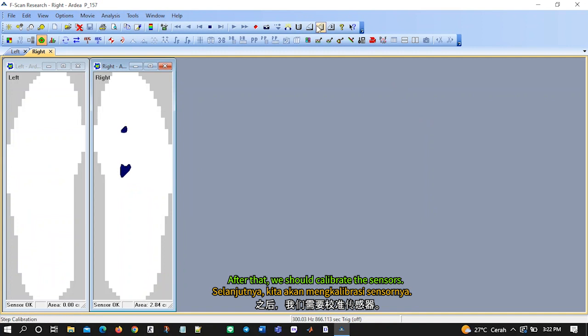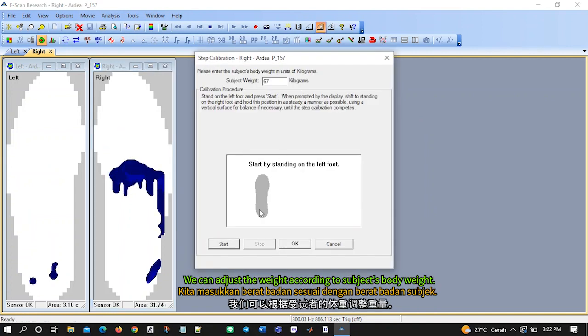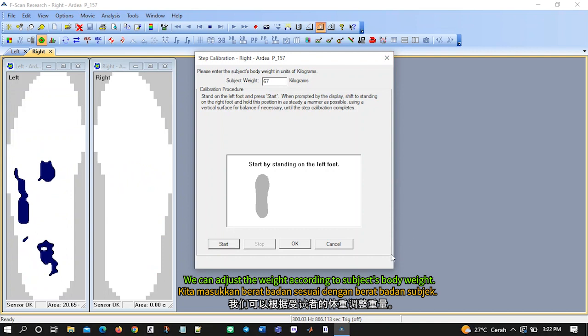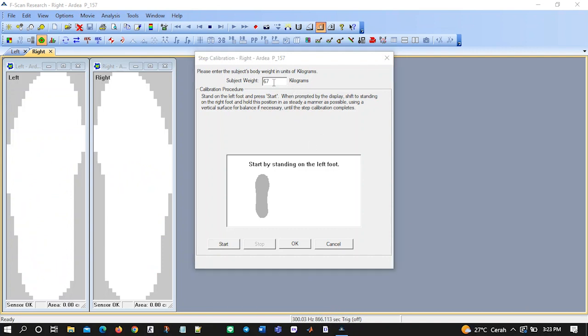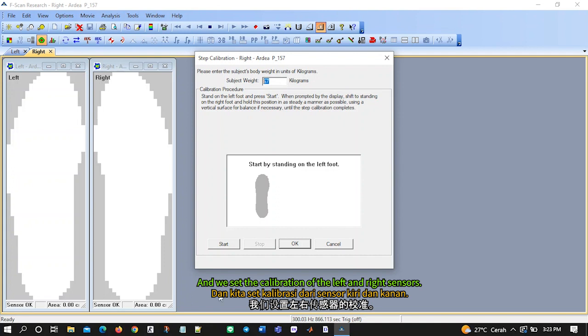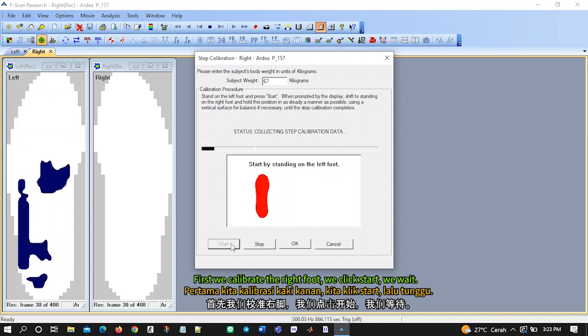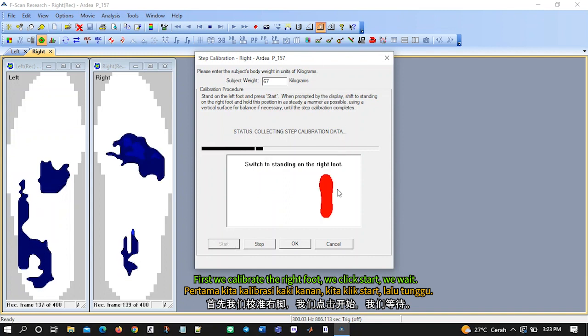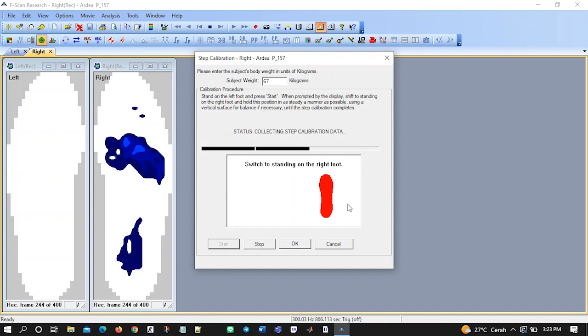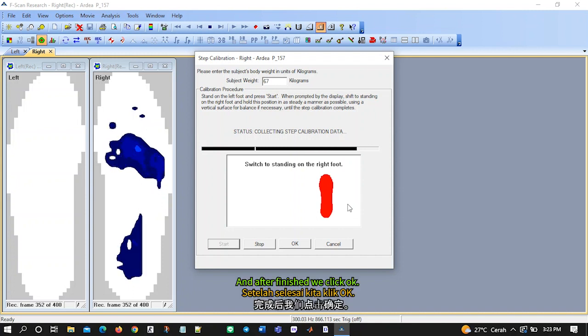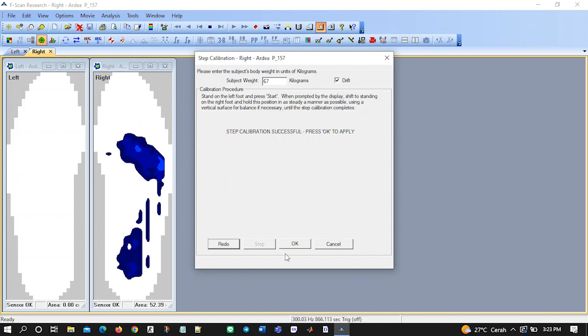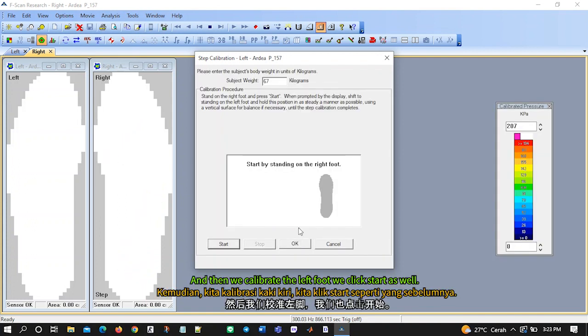After that, we should calibrate the sensors. We can adjust the weight according to the subject's body weight. And we click Step Calibration, and we set the calibration of the left and the right sensors. First, we calibrate the right foot. We click Start, we wait, and after it finishes, we click OK. And then we calibrate the left foot. We click Start as well.